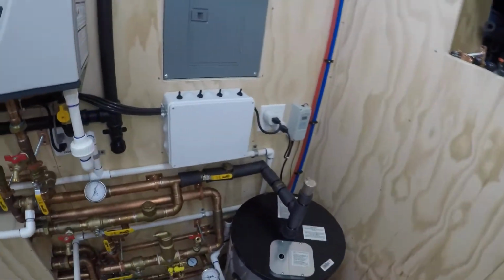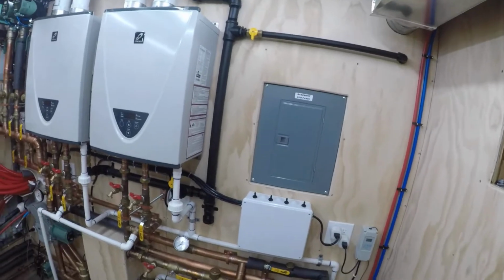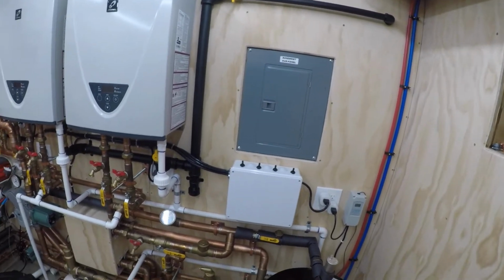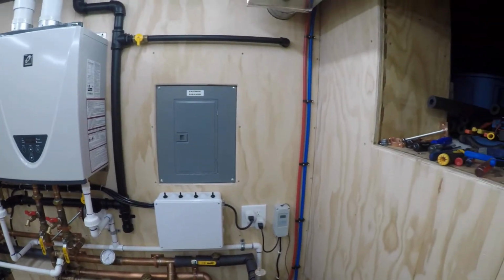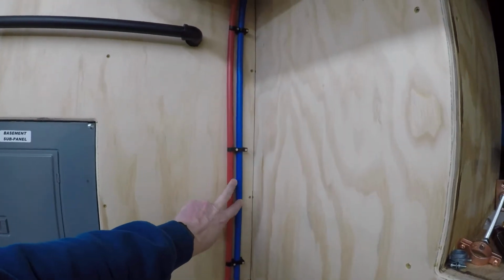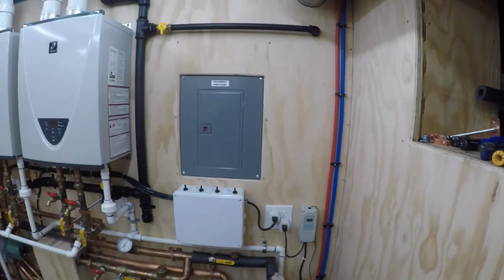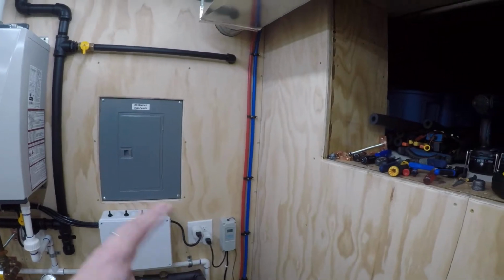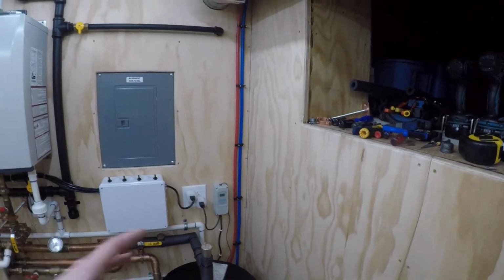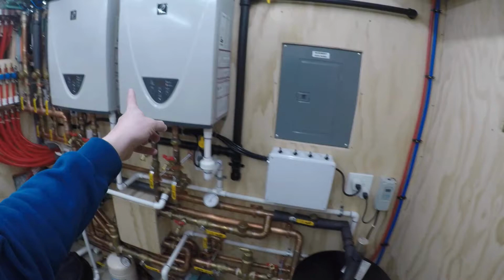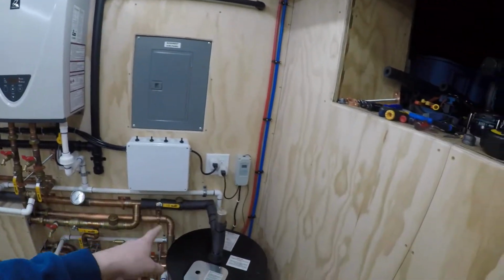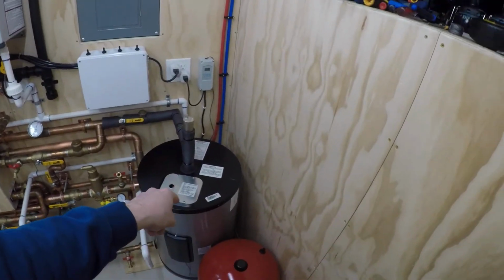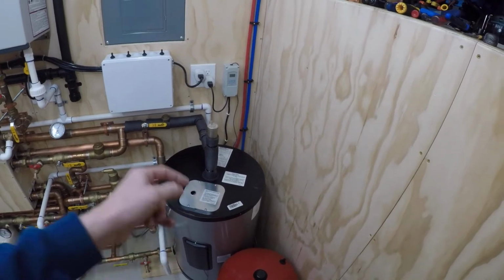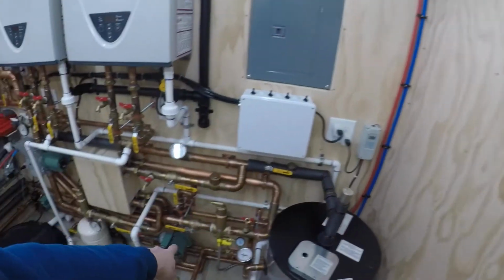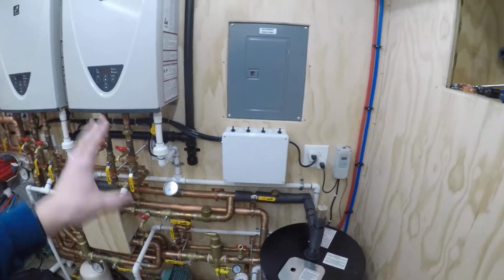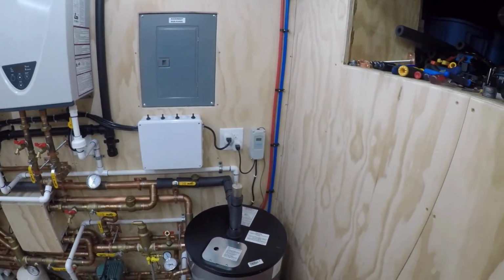And what that does for me is the little calls for hot water, like washing your hands or the dishwasher or the furnace. Our furnace has a whole house humidifier on it that likes hot water better than cold. All of that stuff can operate as it needs, and it's not going to fire the units. The only thing that'll fire the units is when this tank gets below a certain set point. Okay, then that aquastat will turn on that pump. That pump will pump through the tankless units. I'll show you that in a minute.